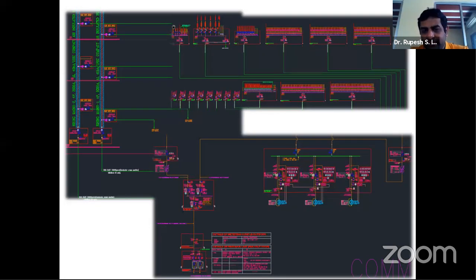So here is just an example of a sample SLD. Like I was saying, these are the DGs. Probably these 3 DGs could become 2 DGs. Instead of 2 transformers, I could have 1 transformer, and so on. All of this cable sizing would come down. All the switchgears, whether my VCB here, my ACB here, or even my MCCBs, all those ratings could come down because my final load requirement has come down. So it's a cumulative effect that will come into play when we design such highly efficient buildings.